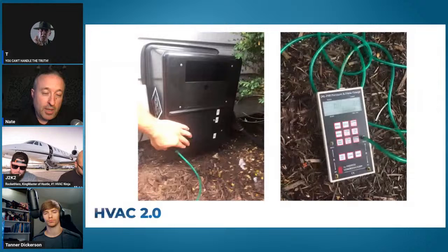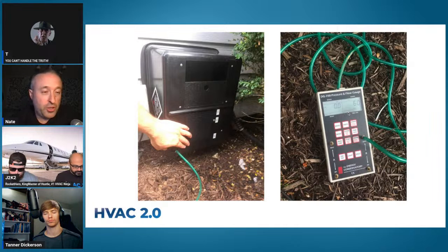Of course, we measure darn near everything. Here's measuring the airflow, and it was pulling 60 CFM with a pretty short and direct duct run. This system had fairly high static, and we didn't really address that at all. It was what it was. The system when I got there was 8 months old, so it wasn't going to get changed.